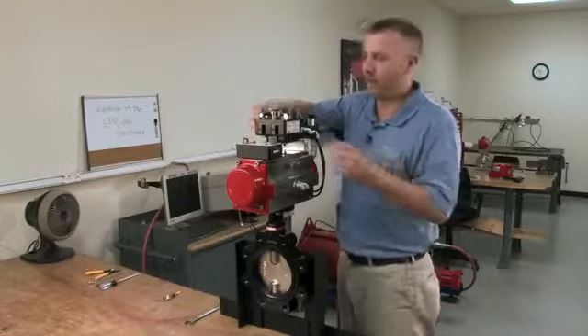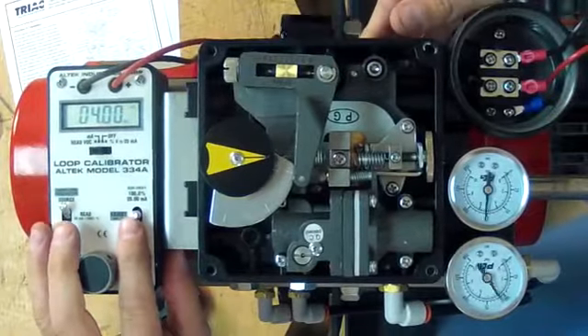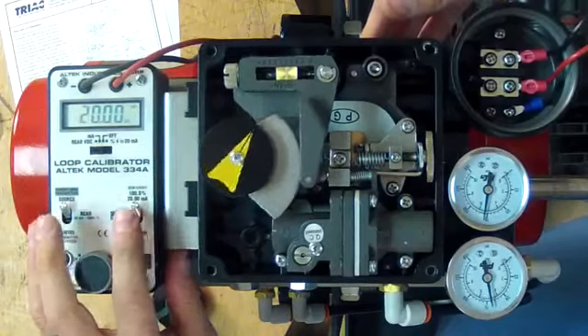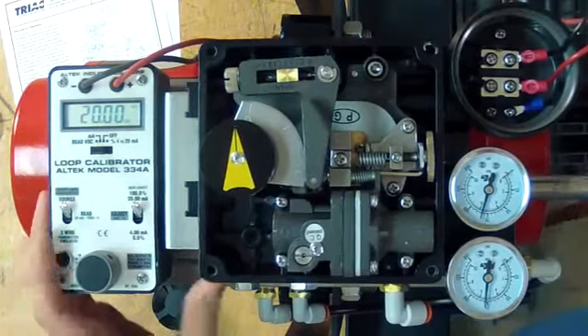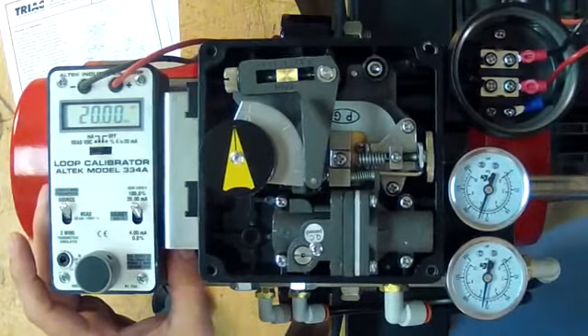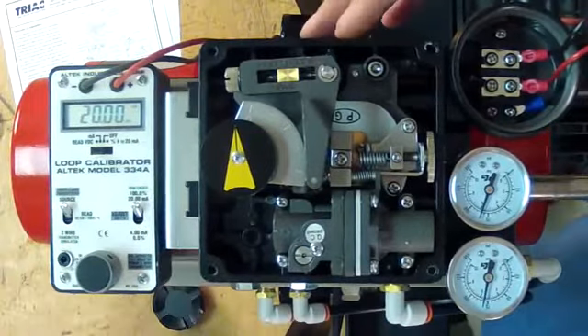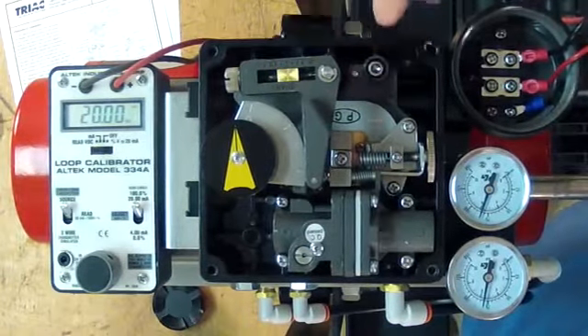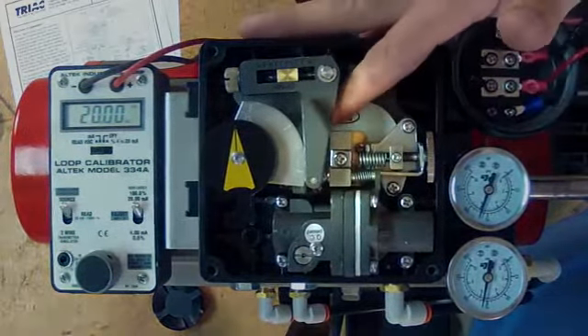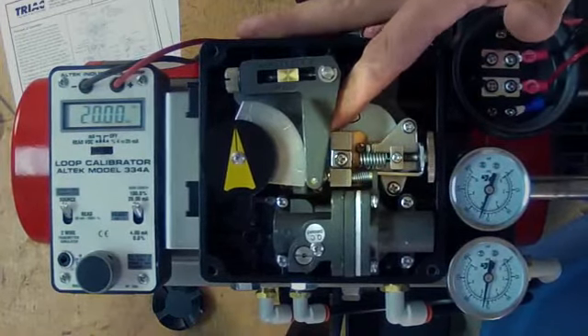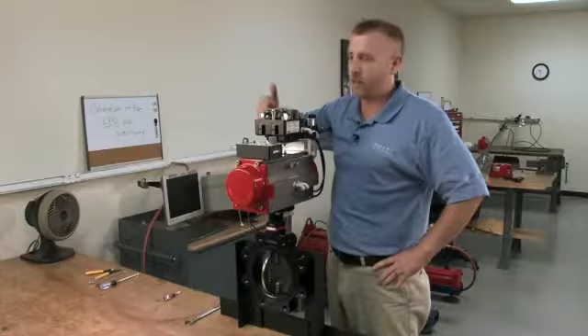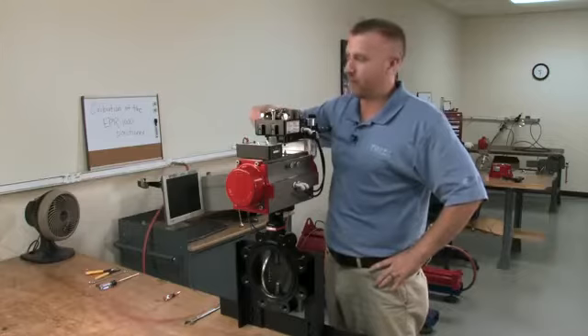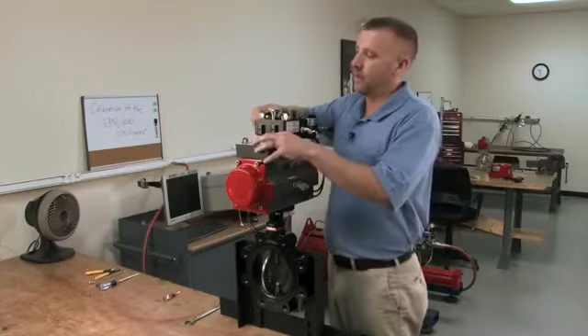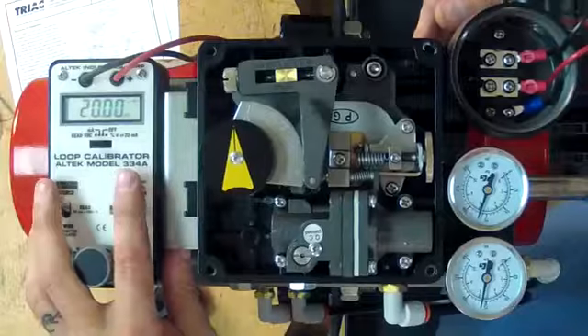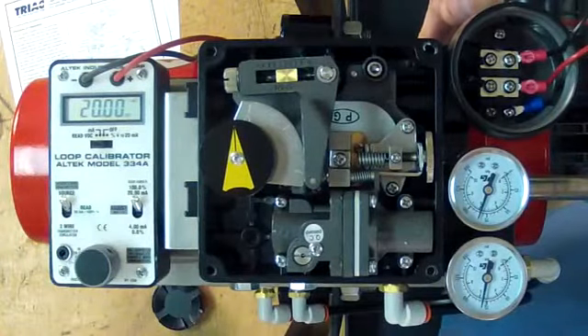Now we're going to run it to the 20 milliamp position. And one way to check for your full open in your 20 milliamp position is your counterweight here. You can pull towards you. And if you don't hear any air bleed off, that means your actuator and positioner are in the full open position. Now we're going to check our mid position by going back down to 4 milliamps, then to 12.